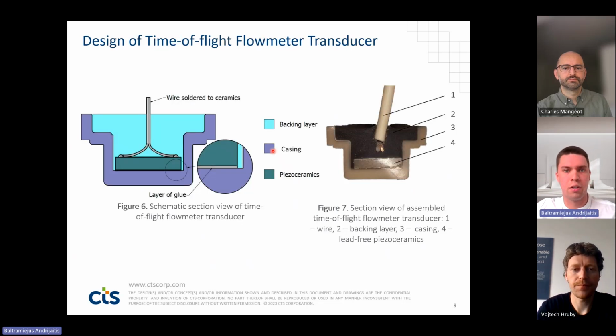Now that we are familiar with the working principle, let's jump to the design. From the first glance, the design doesn't look really difficult. We have wire, we have backing layer, we have casing and active element. However, in general, it's not so easy because we need to ensure a uniform layer of glue. Also, the parallelism between the casing and the active element to achieve the best energy transmission possible. And of course, the thickness of the casing to match the acoustical impedance between the materials and the fluid, where the part will perform.